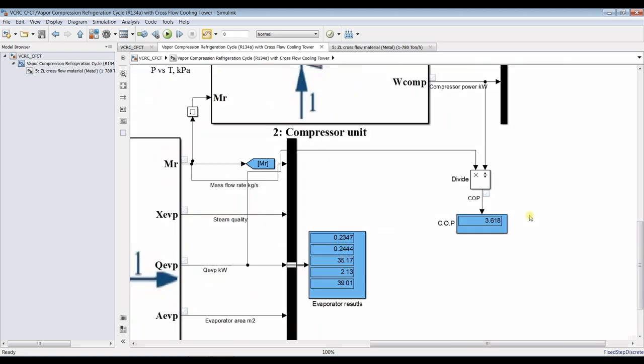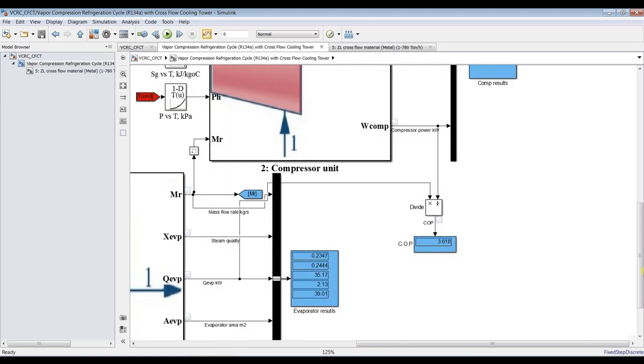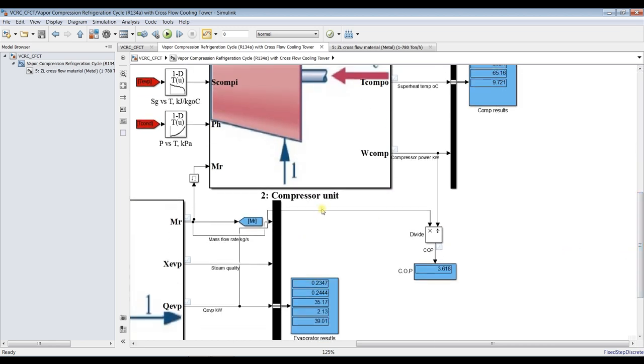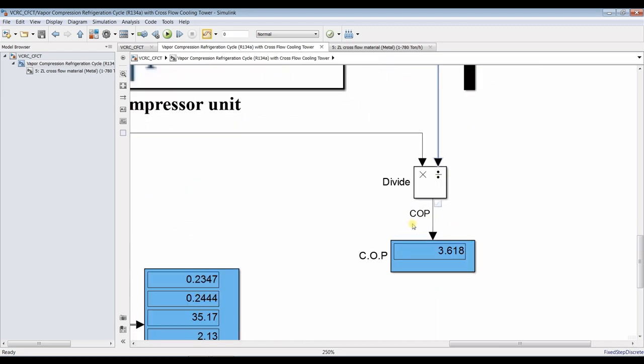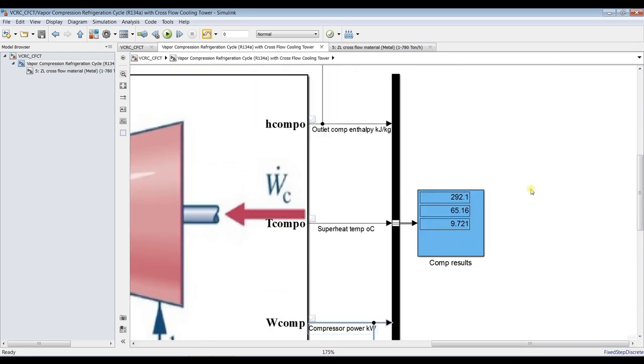And this is your coefficient of performance. Okay, and coefficient of performance is based on evaporator thermal power and the load on the compressor. So if you divide the Q, which is evaporator thermal power, over the working compressor or compressor power, it will give you the coefficient of performance. And we have here the superheat temperature outlet from the compressor. This is enthalpy, I'm sorry, this is enthalpy 292, superheat temperature is around 65, and compressor power is around 9.7.